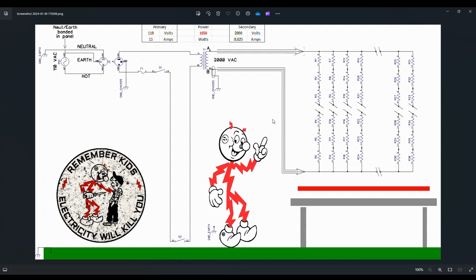So it's still never a good idea to work with these probes directly. Some guys have done it, or they do it. They use PVC pipes with nails in them and things like that. And this wire that we see running up through there is very often a heavy gauge wire, which is stupid because you're only running less than an amp. Period. You're running less than an amp.